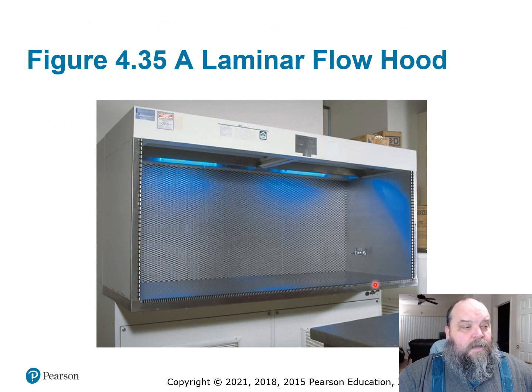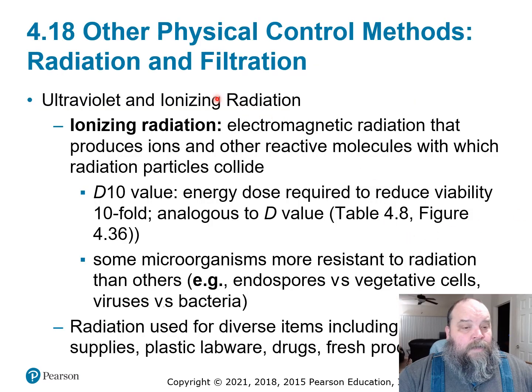That's why you'll see here a safety cabinet where you can do different genetic and microbial work. This perforated panel on the back is blowing air, and there's an air current that keeps stuff from outside getting in. The UV lights you see there are bombarding everything in here and decontaminating the surfaces. Decontaminating, not sterilizing. If you want to sterilize, you need to go with ionizing radiation.